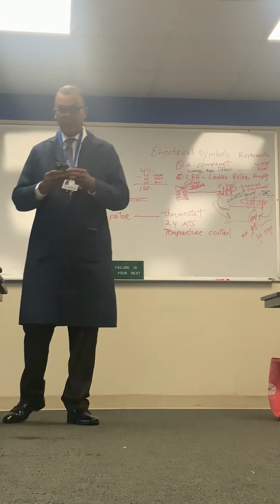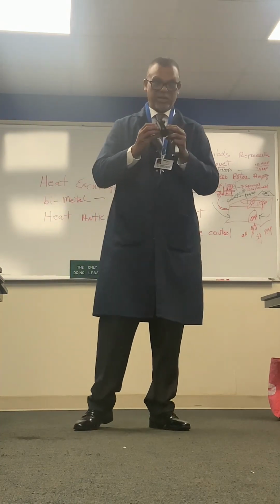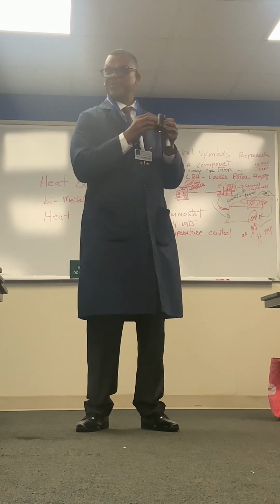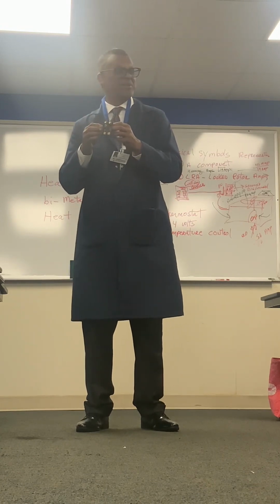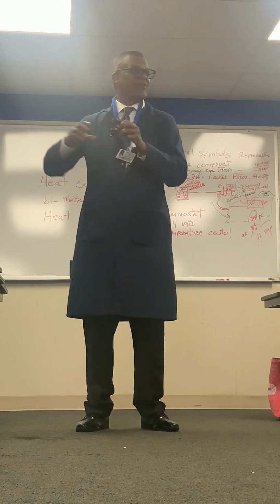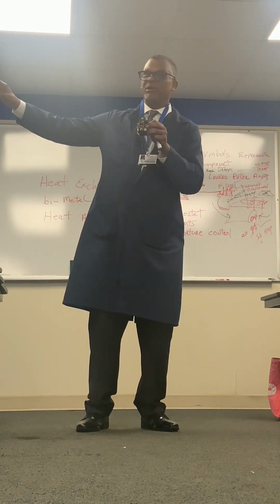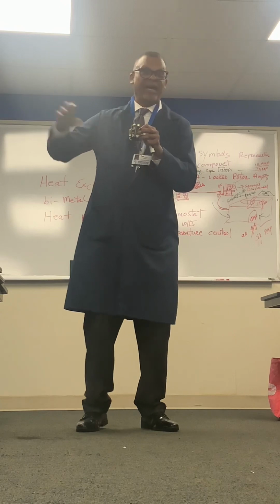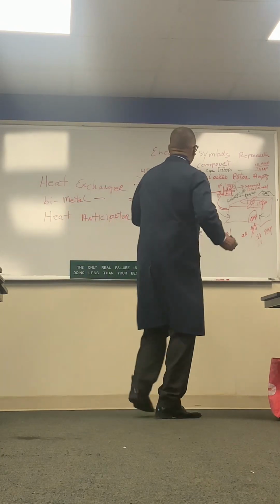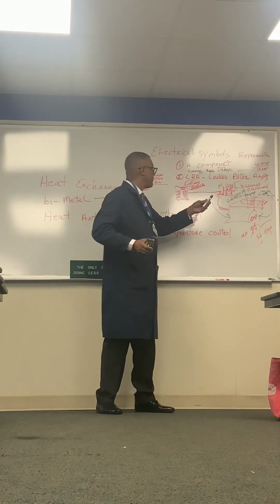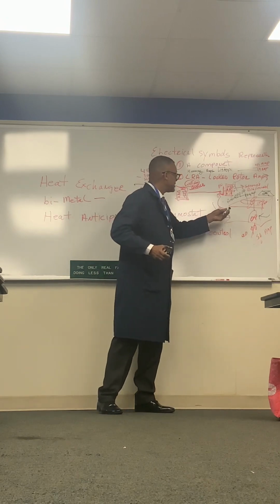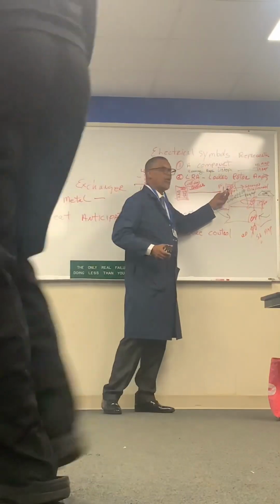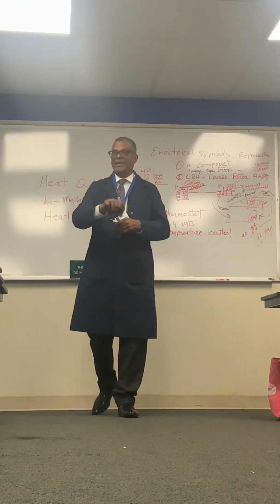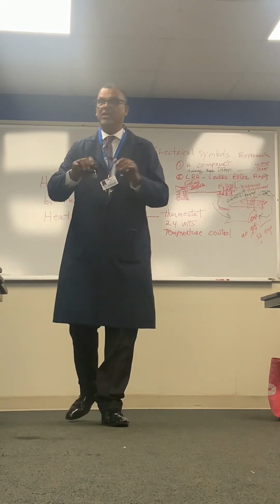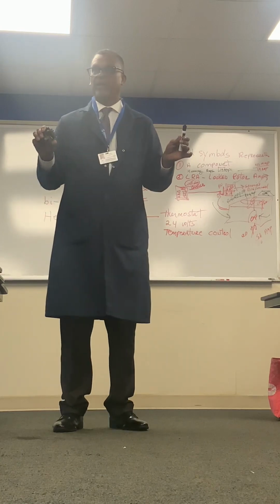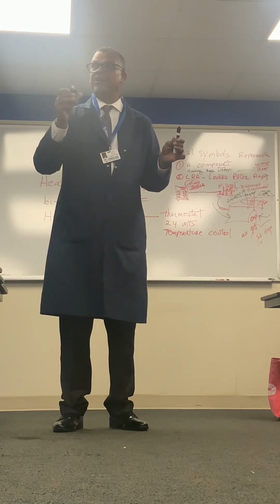Well, the 24 volts that I'm speaking of, Mr. Harris, is the 24 volts that goes to the contactor. I could have accepted that. Because when I have to call for cooling before I get cooling, and I already tested that I have 240 volts at the contactor itself at L1 and L2, but I don't get it to T1 and T2 until what occurs? The contactor has to close.